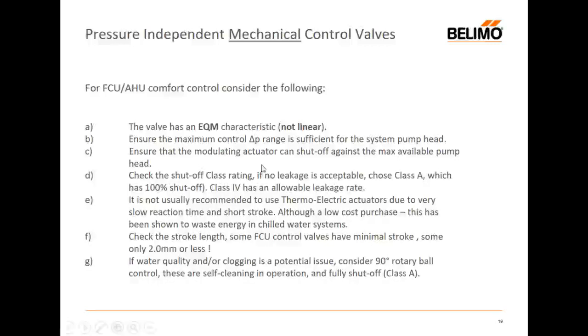And that process can take upwards of 6 minutes, maybe a bit longer. And that's delay. And delay in our business is kind of a bit like waste. Because if I tell the valve to close and I have to wait 6.5 minutes for it to do so, I've got 6.5 minutes where I'm pushing chilled water through the circuit that isn't required. And that's waste and not to be looked for.